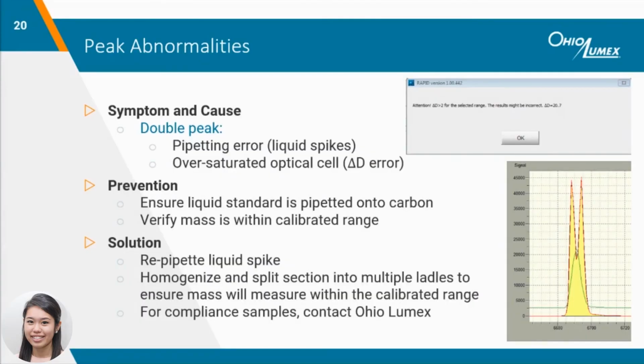When the optical cell is oversaturated with mercury, it usually results in a double peak and an inaccurate reading outside of the calibrated range. This may be coupled with a delta D error warning box as well. If this was a sorbent trap section, run a continuing calibration verification to make sure the analyzer is still running well and there is no residual mercury inside the furnace attachment that could affect subsequent results.